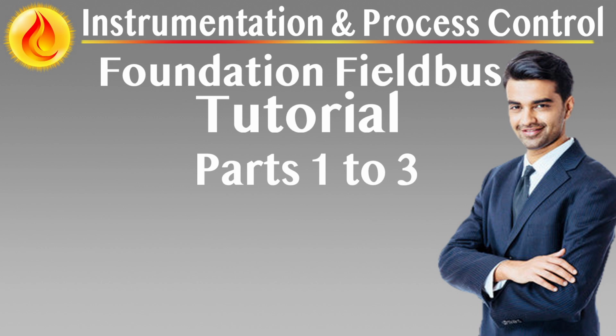communication bus. At the base of the communication model, the physical layer is responsible for transmitting electrical signals over a twisted pair cable or fiber optic medium. It defines voltage levels, signal waveform, cable characteristics, and termination rules. Above this, the data link layer ensures medium access control, addressing, frame validation, and deterministic scheduling via a mechanism known as the Link Active Scheduler (LAS). This layer is crucial in preventing message collisions and managing both scheduled and unscheduled communication across the segment.